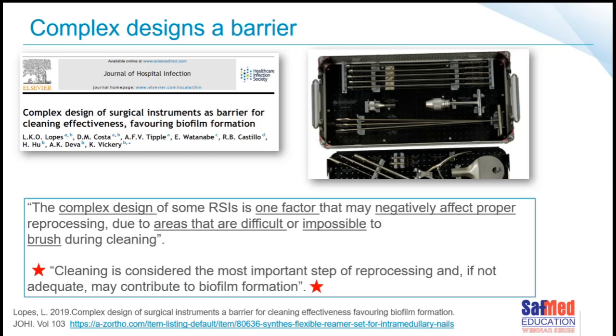In this case, the researchers wanted to see what would happen if they repeatedly do this on the instrument, so contaminate them, wash them using different types of cleaning methods. I'll talk about them now, and then see if, in fact, there was any biofilm formation 20 cycles later. So inoculate, wash, inoculate, wash, inoculate, and test each time in between, doing this 20 times to see after 20 times if there's any biofilm on these instruments.